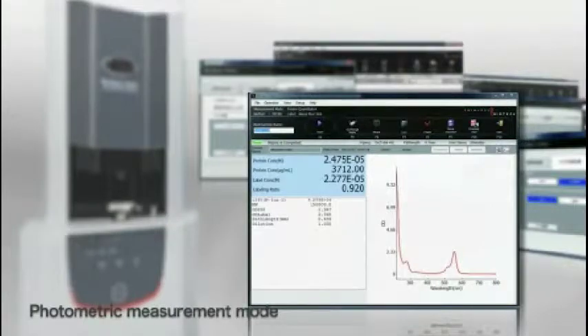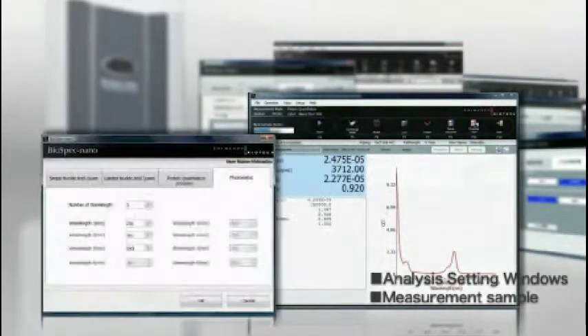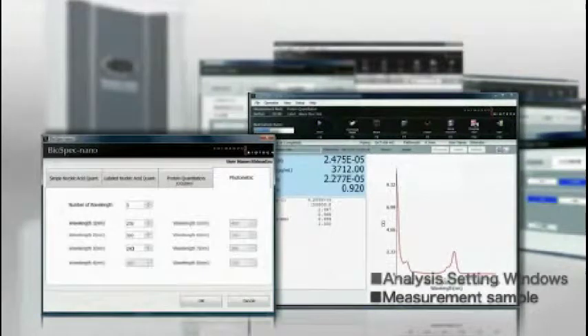This feature allows displaying and printing the optical density values along with wavelengths and optical pathlengths for up to 8 specified wavelengths.